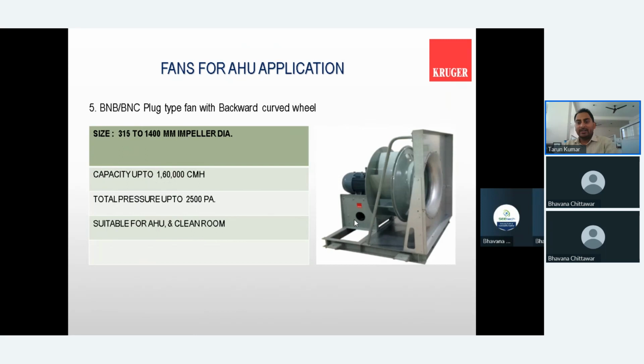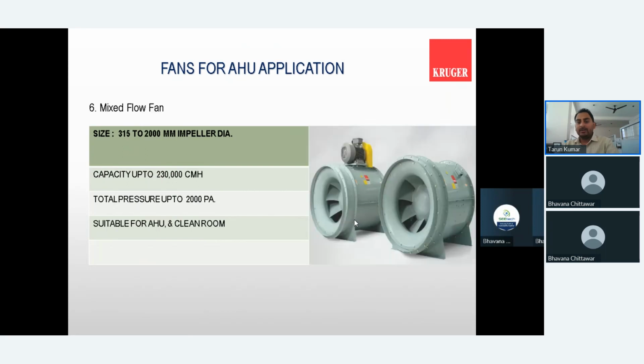So this fan is available with any sort of motor like IE2, IE3, IE4 and IE5. As per your requirement, as per your power saving requirement, you can proceed with the different motor configurations. Further to that, what we have recently introduced for the AHU application is the mixed flow axial fan. This is basically the combination of the axial as well as the centrifugal impeller.